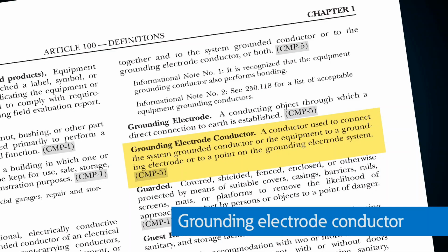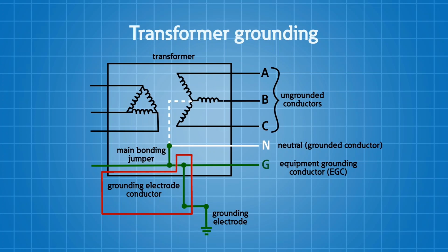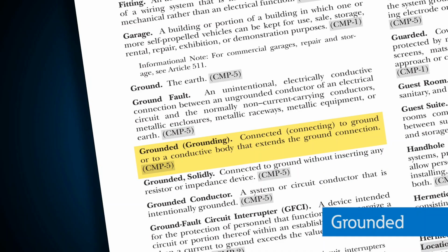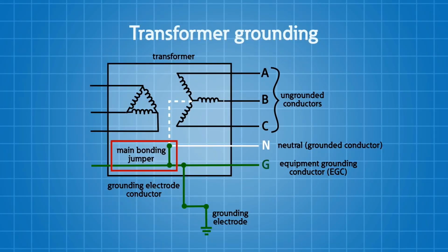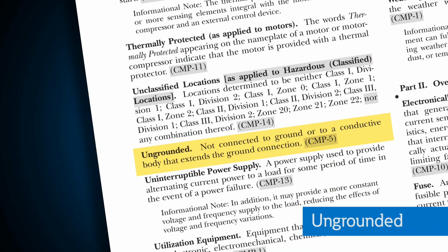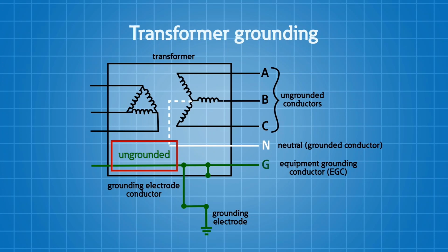Now let's talk about the grounding electrode conductor. This is the conductor used to connect the system neutral conductor, or grounded phase conductor, or the equipment to the grounding electrode system. Grounded, when we use the term grounded, is when we say we are connected to the earth or to some body that extends that earth connection. Ungrounded is just the opposite, right? It's not connected to ground or to a conductive body that extends that ground connection.